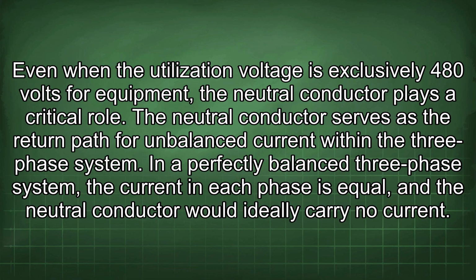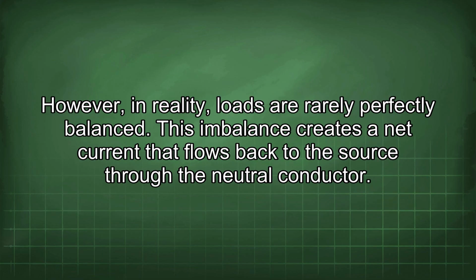The neutral conductor serves as the return path for unbalanced current within the three-phase system. In a perfectly balanced three-phase system, the current in each phase is equal, and the neutral conductor would ideally carry no current. However, in reality, loads are rarely perfectly balanced. This imbalance creates a net current that flows back to the source through the neutral conductor.